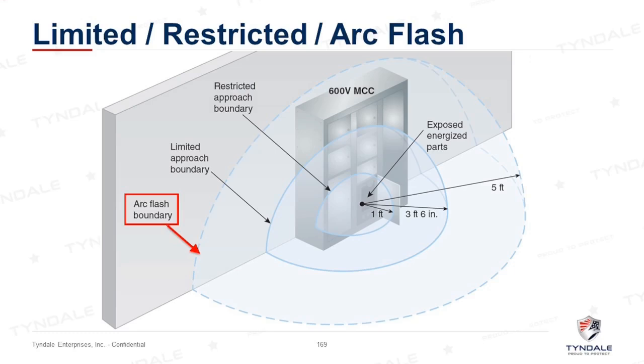Just to refresh: your restricted approach boundary is fixed at the voltage level you're working on, and it's for you as a qualified individual. A limited approach is a fixed level boundary based on the voltage level, and then you've got your arc flash boundary again, which can be completely variable.